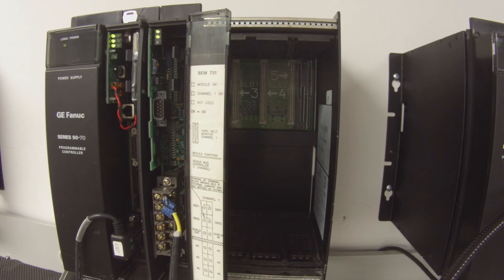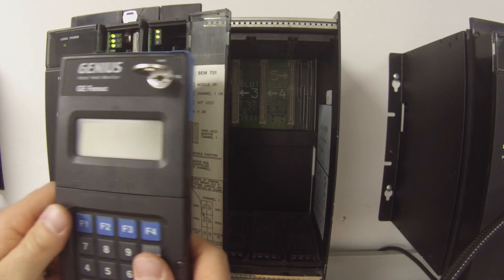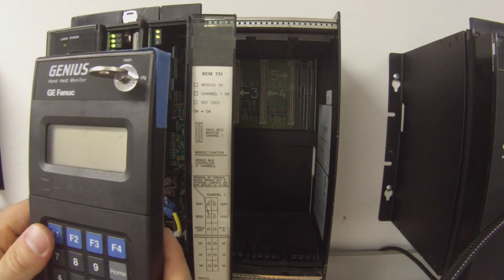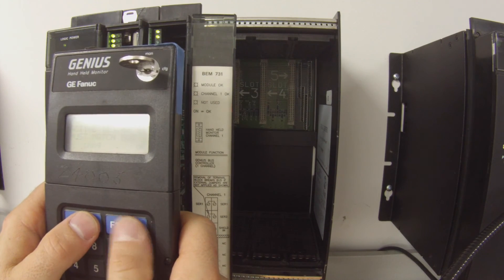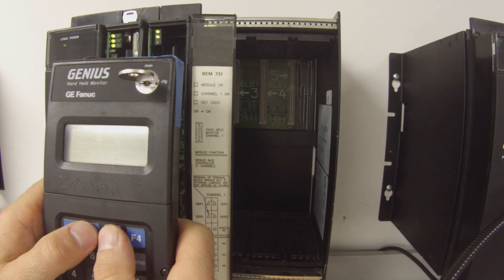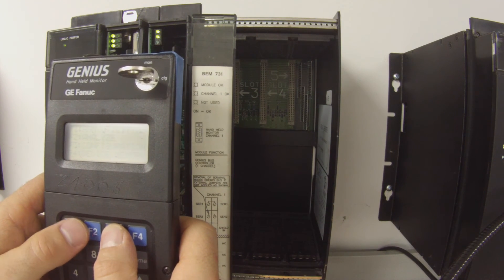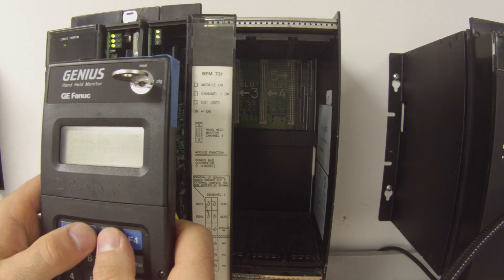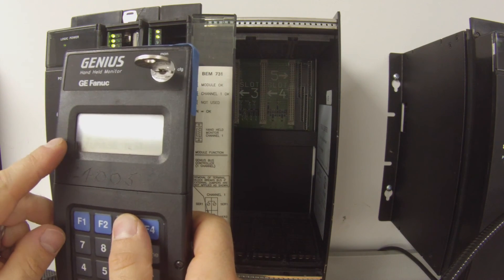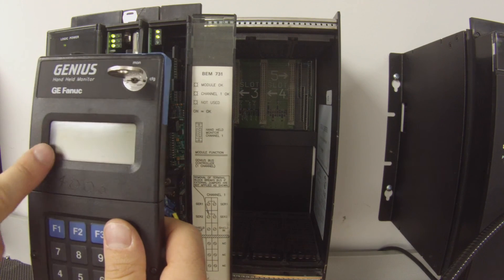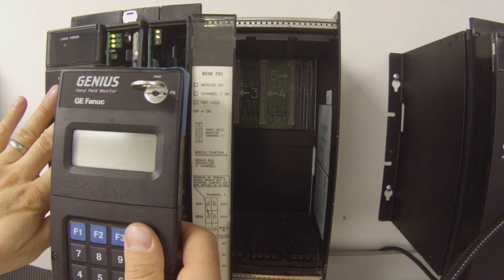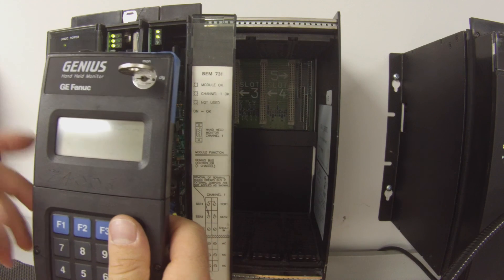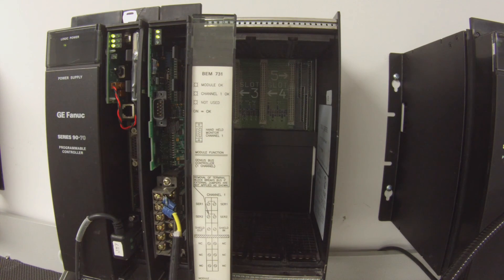So in the event, and this is what it will look like, in the event that we plug in and nothing comes up, it will look like this. So we have the handheld monitor, IC660HHM501, Analyze, F2, F3, Block Bus Status. If that's not working, it will say searching bus, and it will keep searching because nothing is there, if it isn't working. And that's how you'll know the difference.